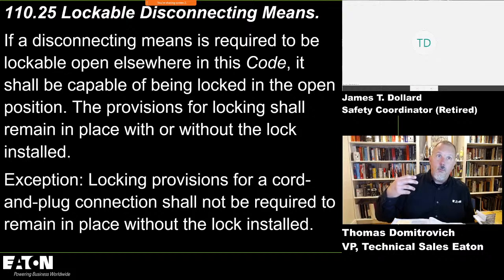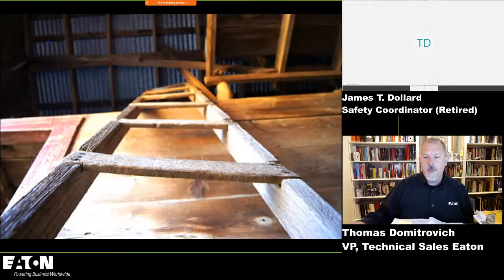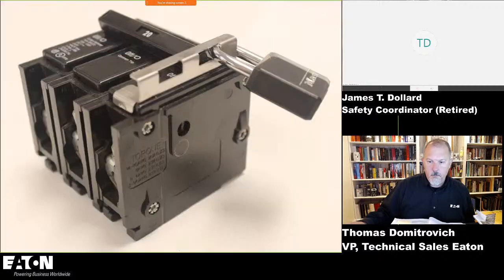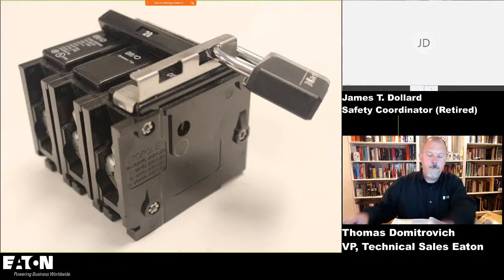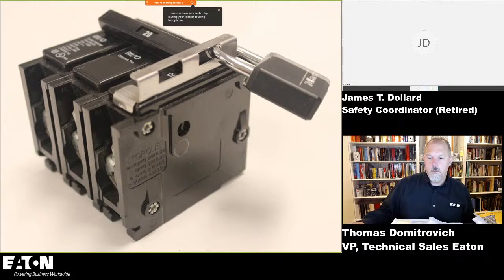And I think I might even have a picture of one of those that are lockable. The key is that the provisions for adding the lock have to remain in place with or without the lock installed. There's a good example from several cycles back. It was Mike Johnson and Donnie Cook and I. We were adding language in dozens of locations, and each committee did it a little bit differently. So the correlating committee said, let's just build a new section in Article 110 to contain those requirements, and wherever we have a requirement for a disconnecting means to be capable of being locked in the open position, they just refer to 110.25.